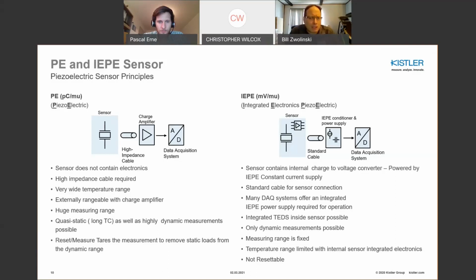With IEPE, on the other hand, you have a sensor that has integral electronics. Obviously, a lot of data acquisition systems nowadays support an IEPE supply right on the data acquisition channel. With this type of sensor, it's usually considered primarily dynamic only. So it's a challenge to preload an IEPE sensor for sure, because the low frequencies are not down to zero. They're usually more AC coupled systems. And then obviously the range is fixed, and as I mentioned, there's really no possibility to measure quasi-statically in that regard compared to the PE.